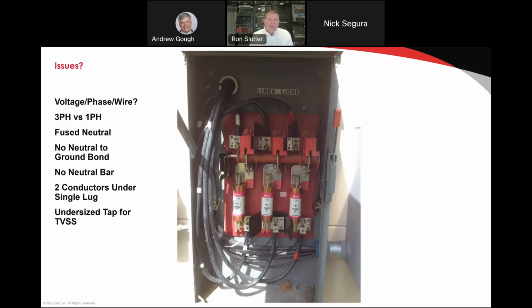If I have to bury a ground rod, let's say I'm in North Dakota, I could have to put that thing down at 40 something inches. How do I get down there to test it? You're going to have to put in a manhole to get down to the ground rod to do testing on your testing intervals. You're not just going to be able to bury it. So there are significant enhancements to the capability and the maintainability of using a chemical ground rod to achieve less than 5 ohms, which is the SCTE standard recommendation that's coming. So yeah, it's very helpful all the way around.